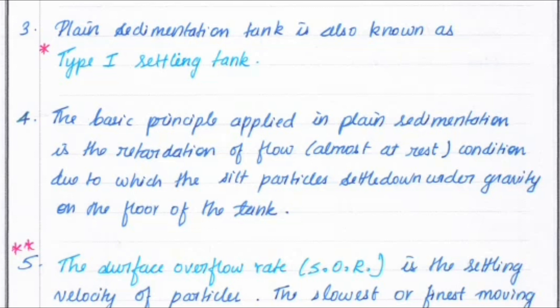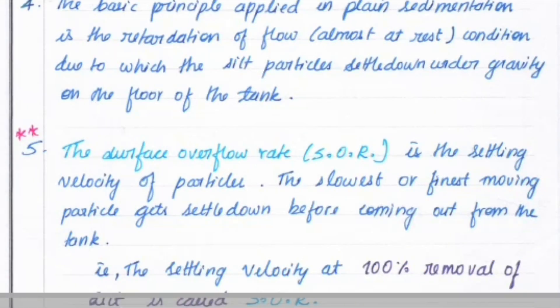The basic principle applied in the primary sedimentation tank is retardation of flow — the condition under which the silt particle settles down under gravity. The most important parameter to consider in the primary sedimentation tank is the Surface Overflow Rate, that is the SOR. This represents the settling velocity of particles, such that the slowest or finest moving particle gets settled down before coming out from the tank.